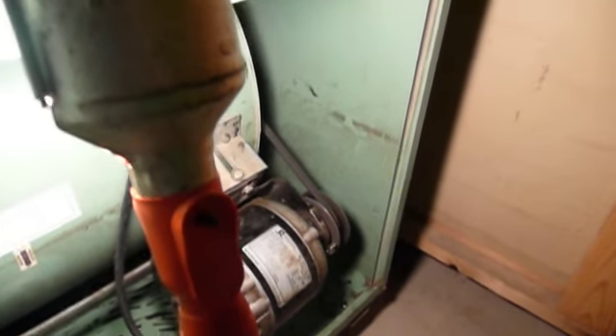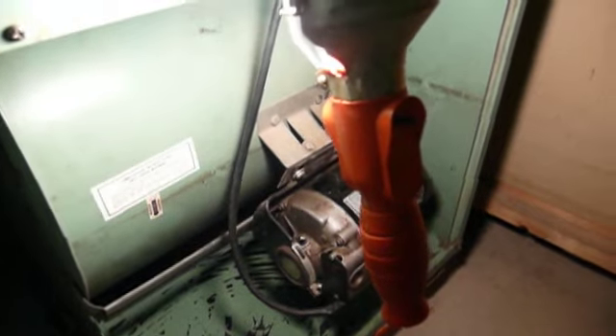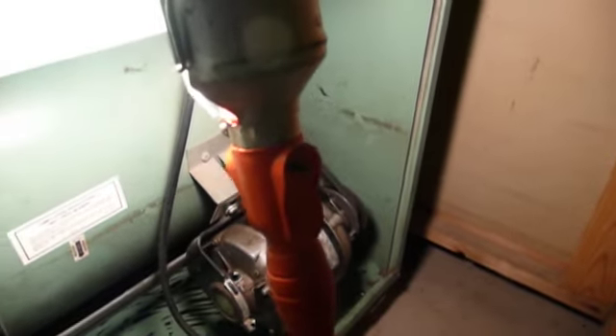That's running quite a bit better now, moving a lot more air. I had the circuit breaker shut off — still need to get a new belt, but that ought to get him through the night. Just keep an eye on the ice in there — should be all melted soon. Starting to look normal again. That's probably the most water coming out of that thing in a long time. And there are some chunks of ice that just vacated the refrigerant piping.